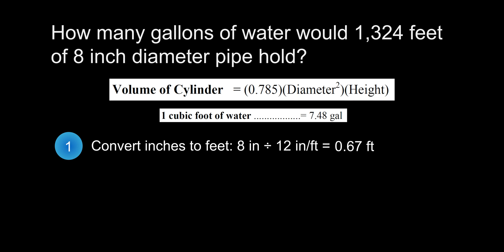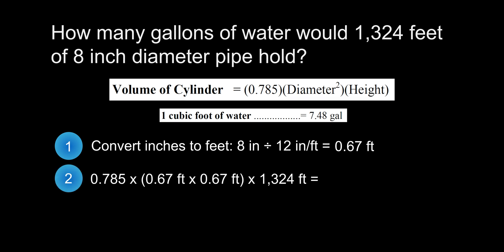In the next step, because a pipe is a cylindrical shape and we need to know the volume that it can hold, we will use the volume of a cylinder equation. So let's plug our numbers into it: 0.785 times the diameter squared, which is 0.67 feet times 0.67 feet, multiplied by 1,324 feet — the length of the pipe — gives us 467 cubic feet.